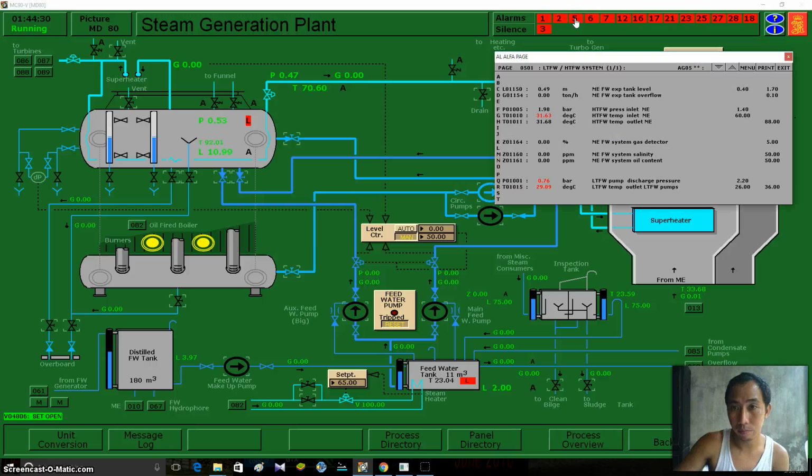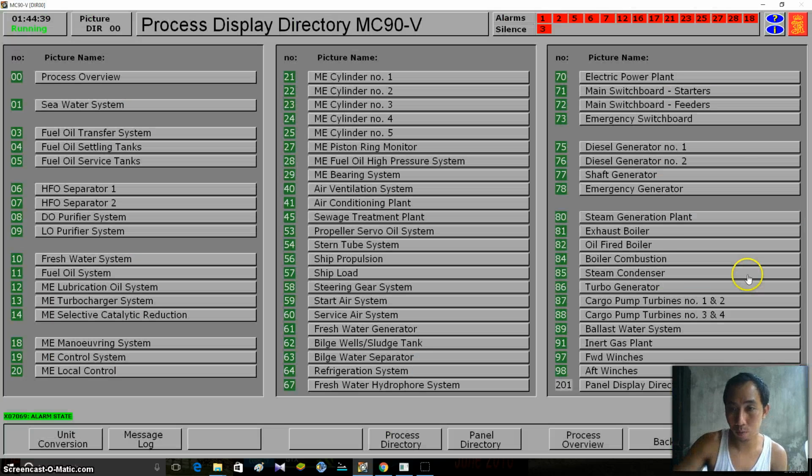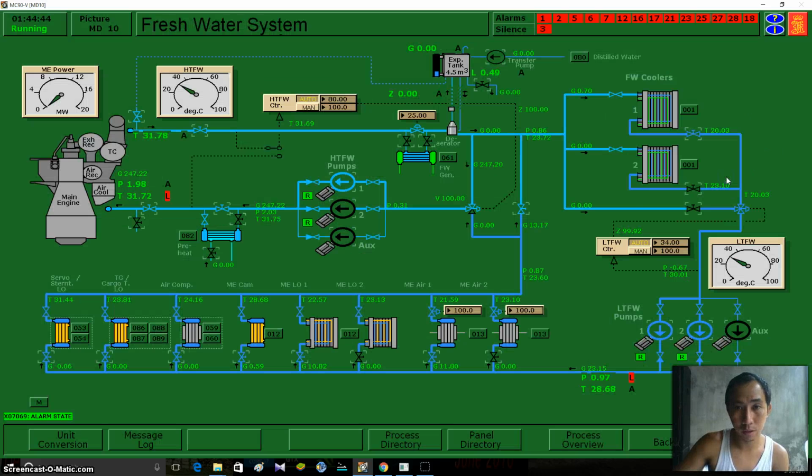We're going to check the alarm. So low temperature, we're going to check what problem we have there since it always occurs. So we're going to check our cooling system. Okay, so this is the problem. So we're going to open this one. One pump, I think, is enough.